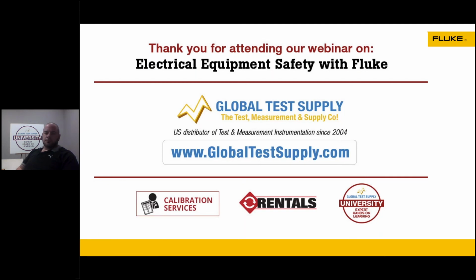Now with fused probes, that's a different story. The fuse itself is trying to save the fuse within your meter. A lot of schools will do this. If you've got an education meter and students, maybe the instructor doesn't want to break into every meter every time to change the fuse. They'll put an inline fuse prior to that, so that's what has to be replaced. But that doesn't change your category rating. It's just saving the meter from that inline current running through it.